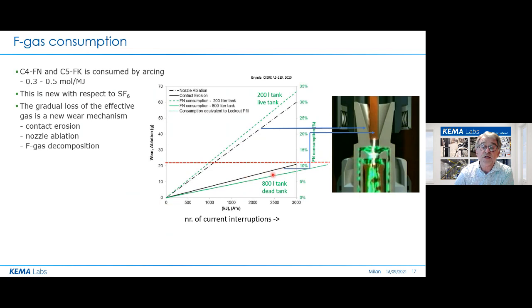So it will reach the limit long after the limit of wear of the nozzle has already been reached. But the important feature here is, of course, where does the F-gas reach the limit of its wear? Here we see this will depend on the volume, on the amount of F-gas which is inside of the breaker.